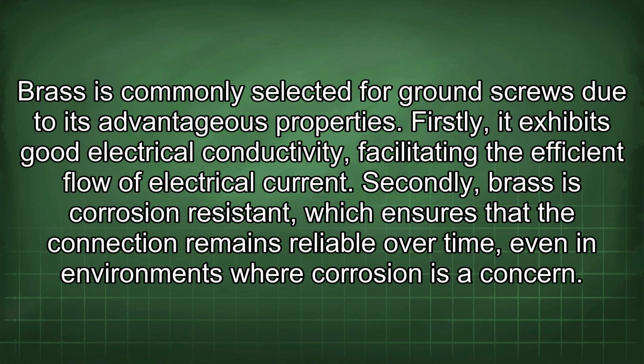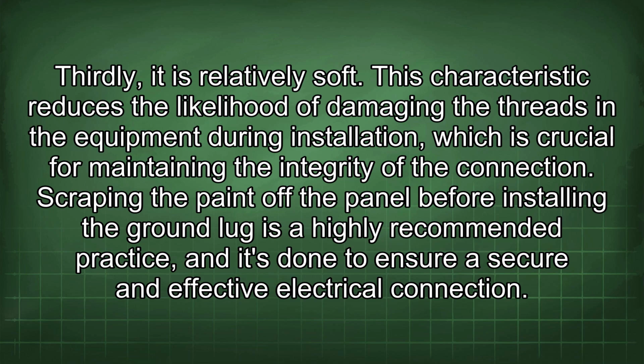Brass is commonly selected for ground screws due to its advantageous properties. Firstly, it exhibits good electrical conductivity, facilitating the efficient flow of electrical current. Secondly, brass is corrosion resistant, which ensures that the connection remains reliable over time, even in environments where corrosion is a concern. Thirdly, it is relatively soft.